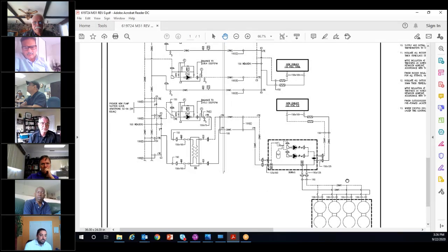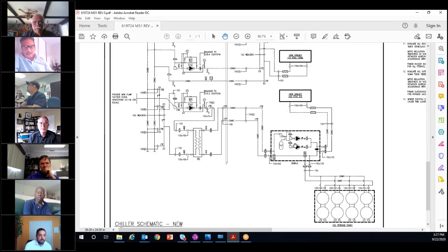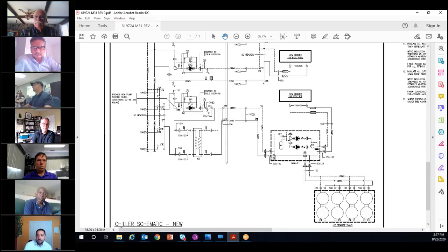And the second chiller was put into a glycol loop. You can see the chiller here, the ice pumping module and the tanks are all on glycol, all connected through a new heat exchanger inside the building, then having water on the other side tied into their existing system. So this chiller, as part of the ice system here, can either create sub-freezing glycol to freeze the tanks at night, or it can work in conjunction with the tanks to provide cooling to the hospital during the day. And the strategy for when you use that really hinges on the strategy that you're trying to use. In this case, we were trying to reduce the operating cost by load shifting and using less kilowatt hours during peak hydro rate times.